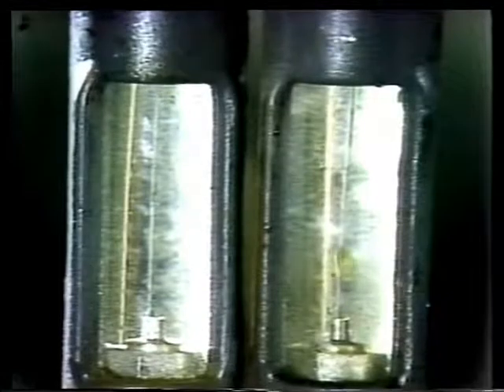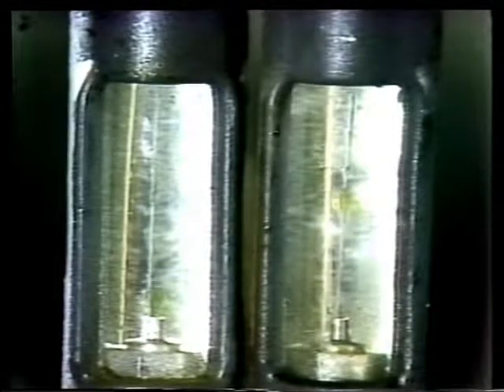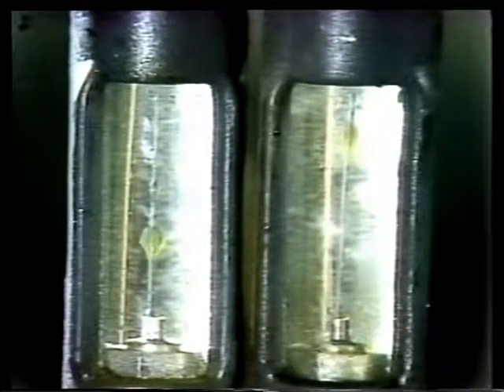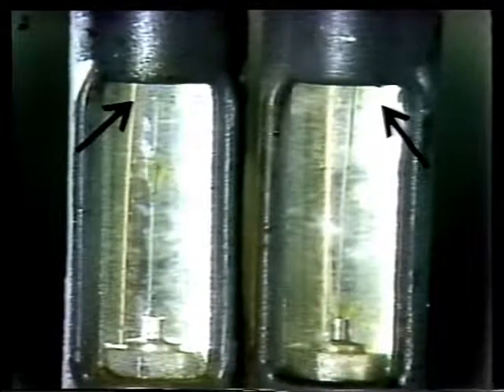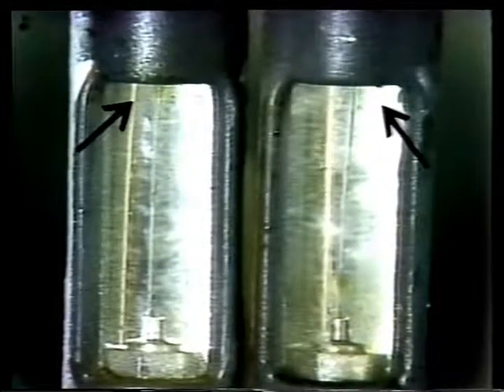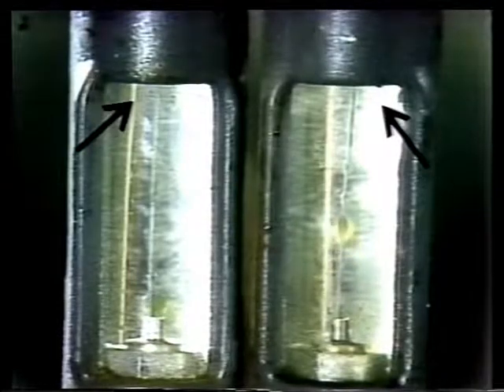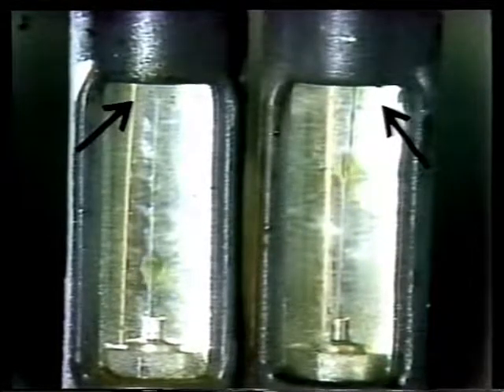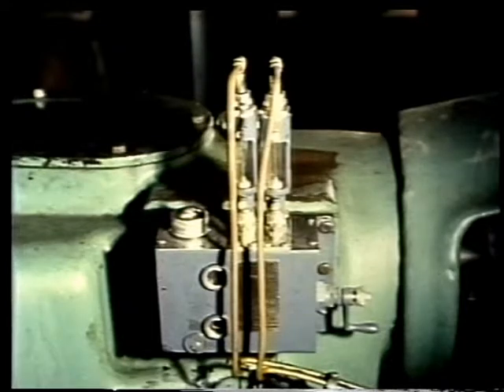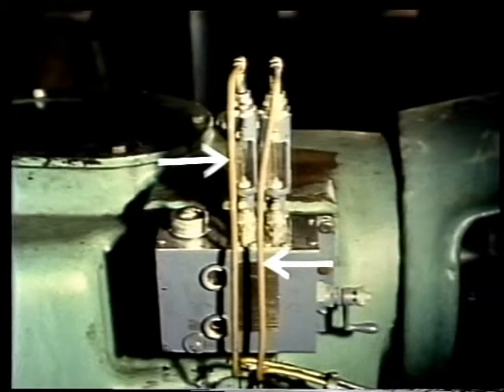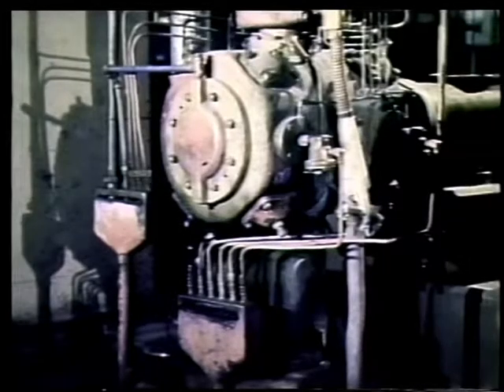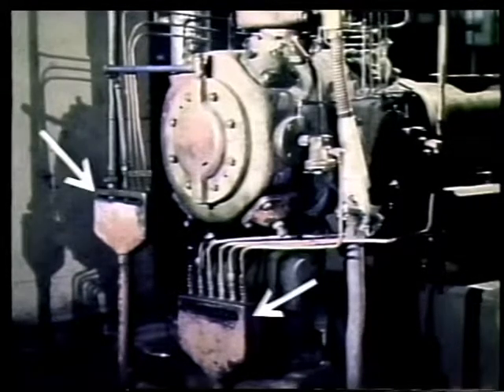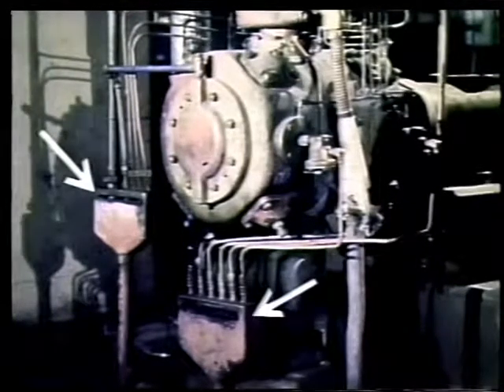If the supply is blocked by dirt or sludge, the rate will slow down, or in severe cases, oil will pool on top of the glycerin. That's the mixture that fills the sight glass. If this is the case, no oil is reaching the cylinder, so you have to stop the compressor and clean out the oil lines. On many air compressors, cooling water flow is just as important as lubrication. The discharge line funnels should receive a steady flow of water from the water jackets and intercooler at all times.